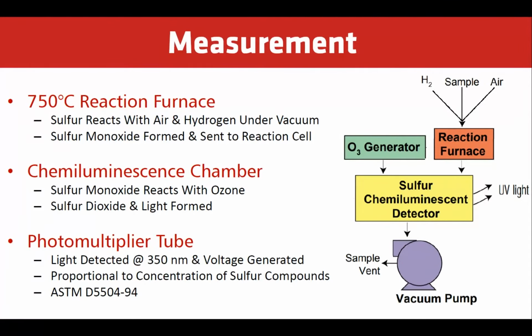So basically you have your sample, your hydrogen, and your air in the oxidation reduction or the reaction furnace. Ozone is generated, and it all comes together in the sulfur chemiluminescence detector, and it produces UV light. And this is all done under vacuum with the vacuum pump.